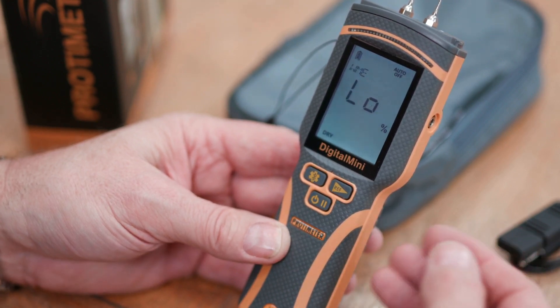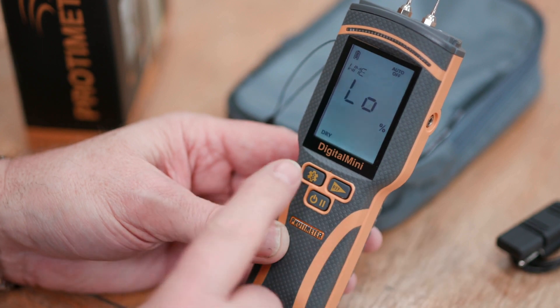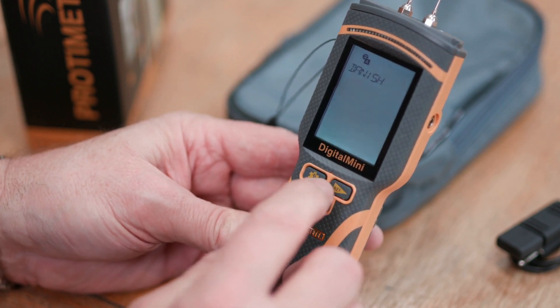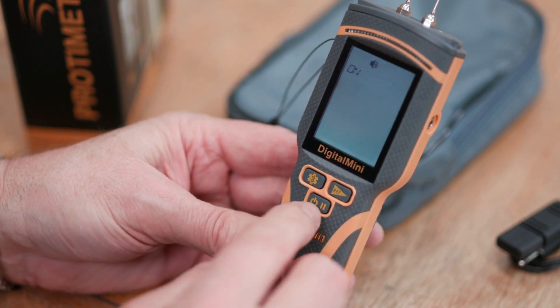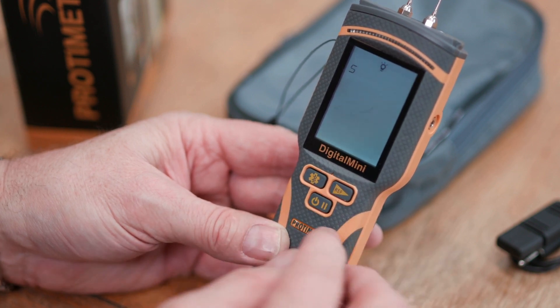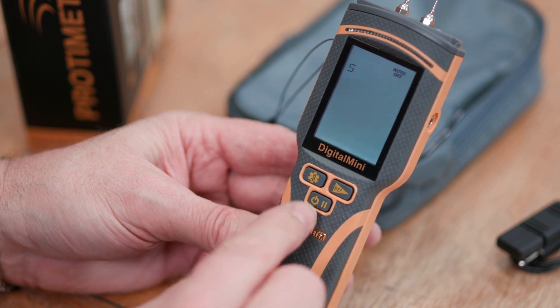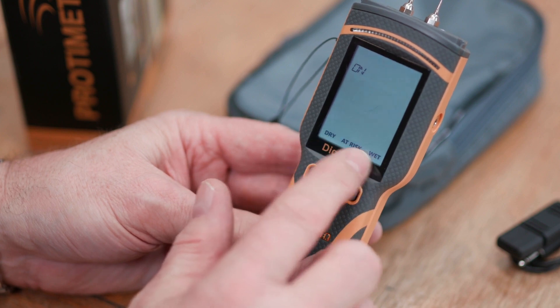The Protimeter Connect app allows you to download, record, and share readings from this moisture meter. In the settings menu you can select different languages, turn the beeper on or off, adjust the display brightness — up to 10 for bright sunshine — set auto-off up to 10 minutes or disable it, and turn the dry, at risk, and wet zone functions on or off.